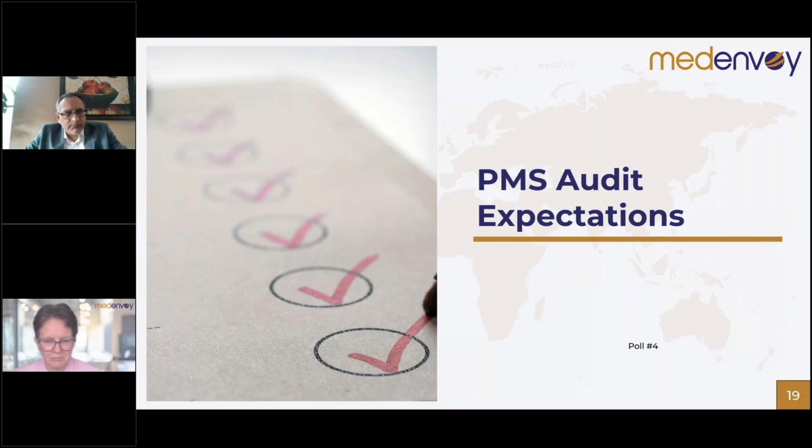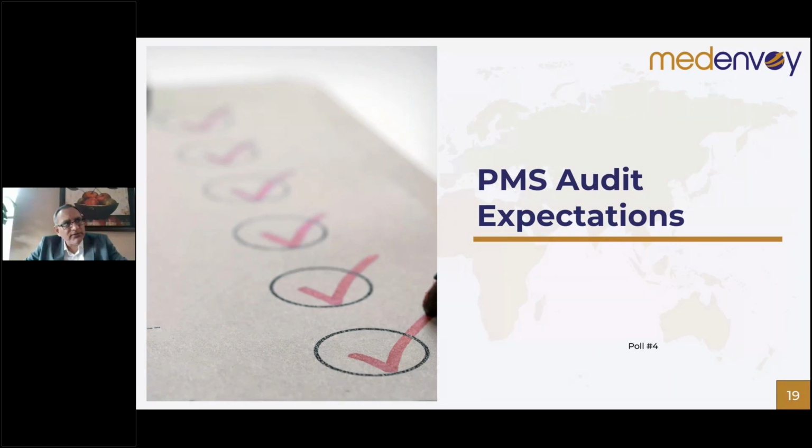So one of the poll questions, I think it's important that we emphasize the post-market clinical follow-up as well. Post-market clinical follow-up is part of the post-market surveillance system. In years gone by, in the previous regulatory regime, if post-market clinical follow-up was not required, manufacturers used to just verbally, anecdotally inform the auditors that it's not required, it's established technology, there's no residual risk, and to a greater extent that was acceptable. However, under MDR, anything of that nature is not acceptable anymore.